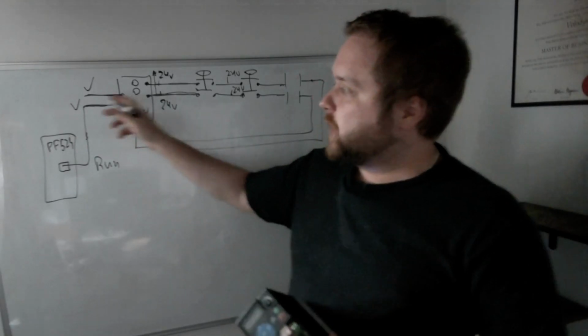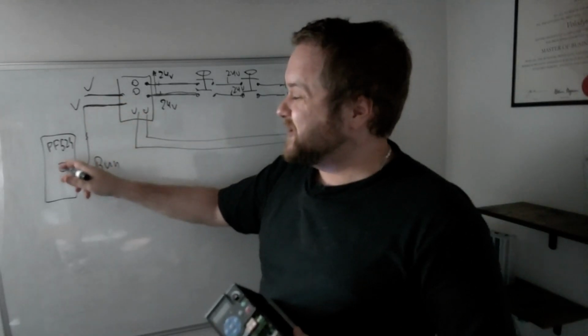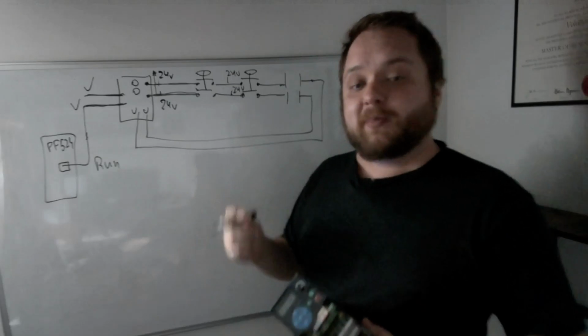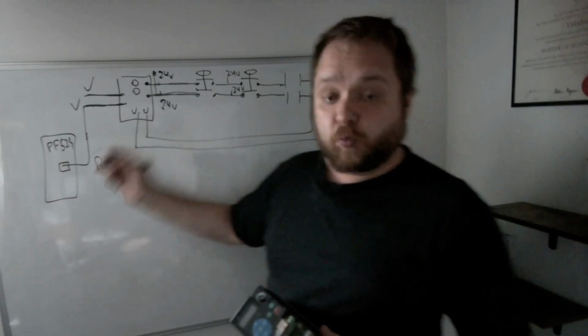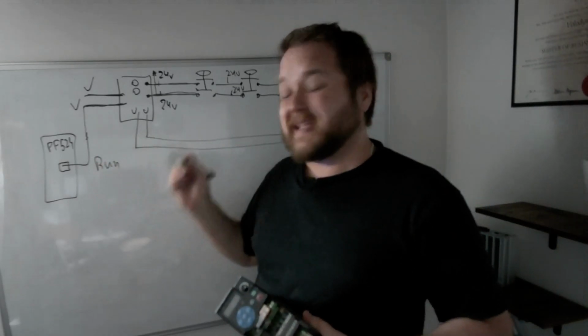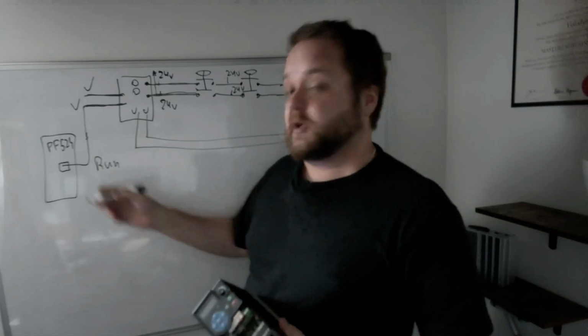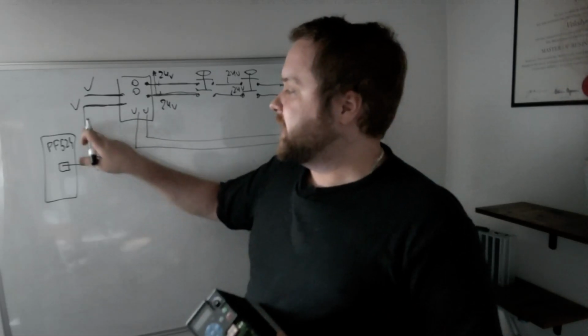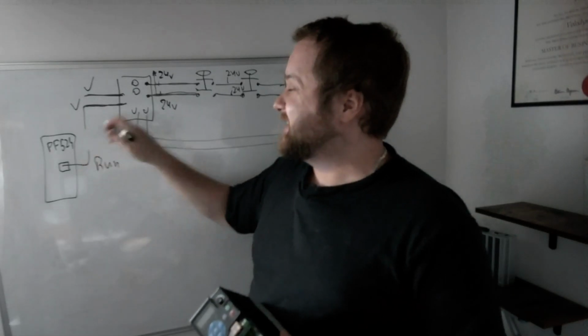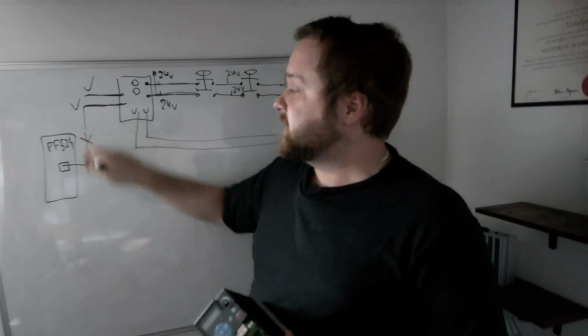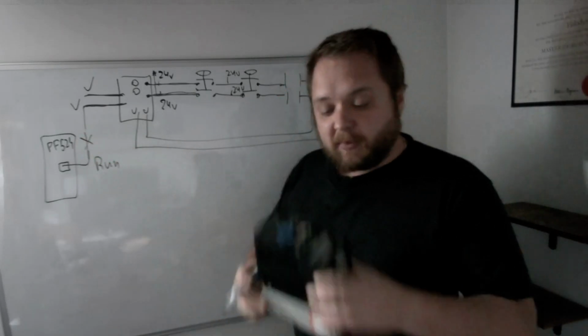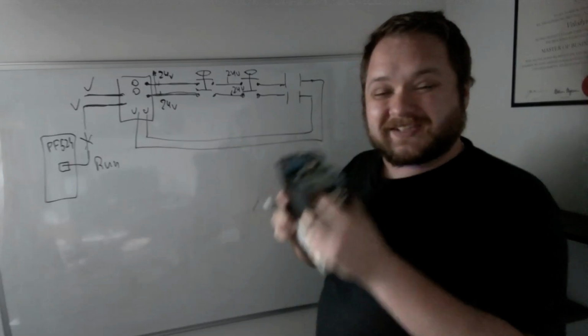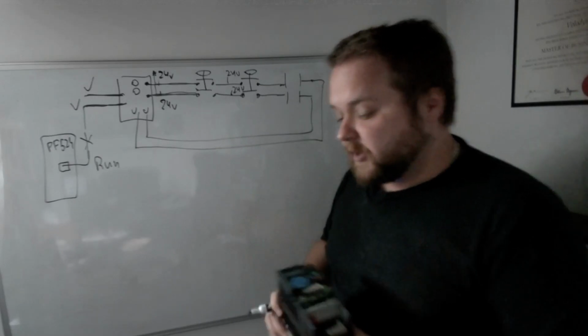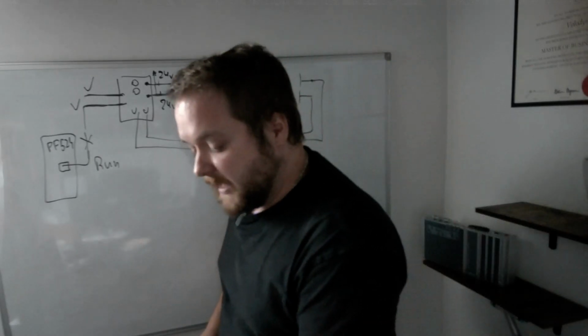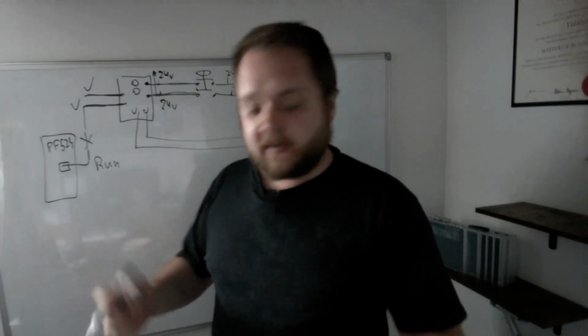So if you just wire in your safety relay into the run command and you leave the jumper in, the PowerFlex will run, but this will not be a safety rated application. Obviously, once this breaks, right, so if the safety relay becomes unsafe, it's going to break the signal and the PowerFlex will stop. But it is important to use the safety rated inputs for all of your devices. And the same can apply to a variety of different things.